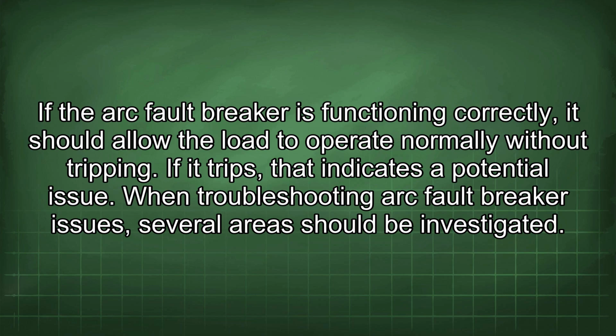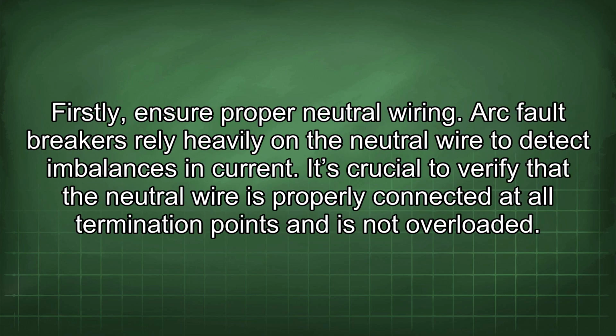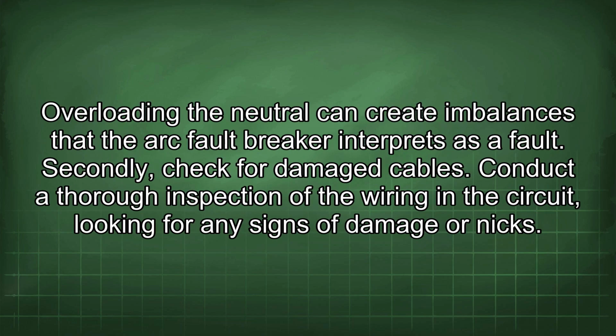When troubleshooting arc fault breaker issues, several areas should be investigated. Firstly, ensure proper neutral wiring. Arc fault breakers rely heavily on the neutral wire to detect imbalances in current. It's crucial to verify that the neutral wire is properly connected at all termination points and is not overloaded. Overloading the neutral can create imbalances that the arc fault breaker interprets as a fault.